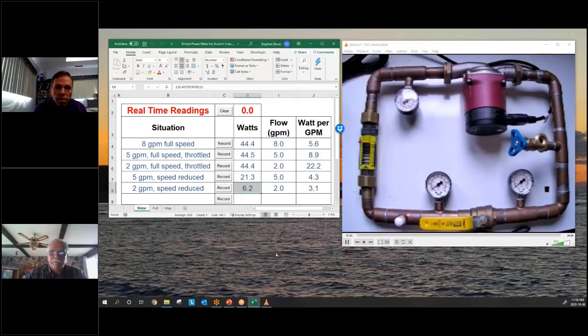Yeah, absolutely. And what about the valve that's not a throttling valve but gets used for that and kind of lurks and hides away? What's that called? The triple duty valve? The circuit balancing valve? Or the triple duty valve? Oh, the triple duty valve, yeah. So the triple duty valve, you will not remove the triple duty valve, by the way. You will keep it because it has triple duty, but you will open it up completely and check the number of rings.